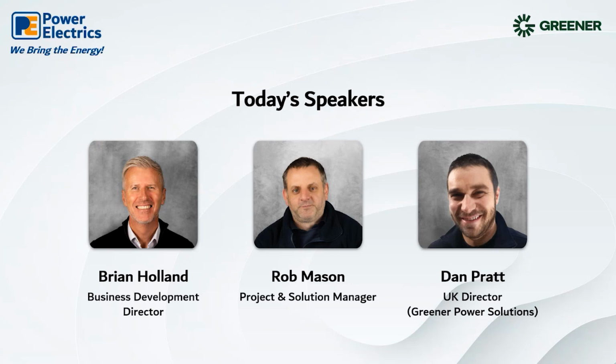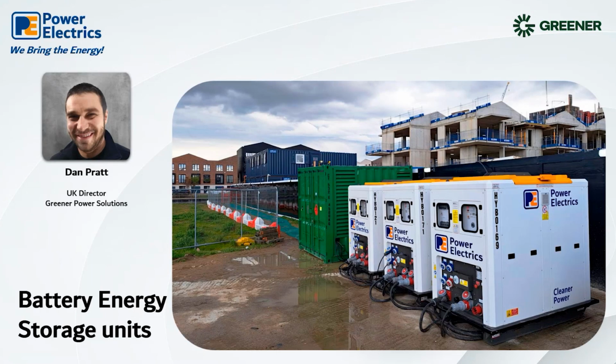A couple of examples of this would be a tower crane or a mobile MRI scanner. These require huge peak power when the crane is lifting or slewing, or the scanner is scanning. However, when these machines are at idle, the power demand is almost zero. In fact, from data we've gathered, a crane will only use between 20 and 100 kilowatt hours of actual energy in a day. To run a large generator, usually between 200 to 500 kVA, to be capable of powering these short peak power demands would be incredibly inefficient.